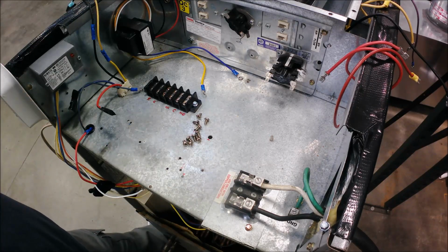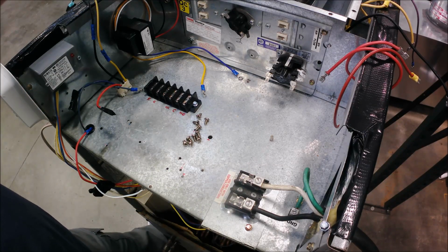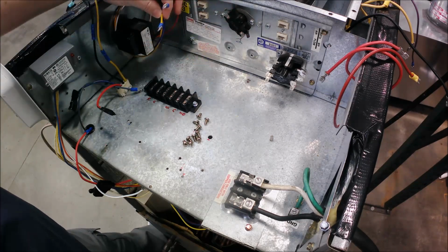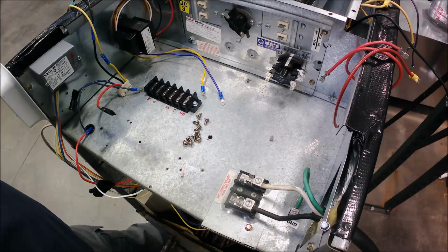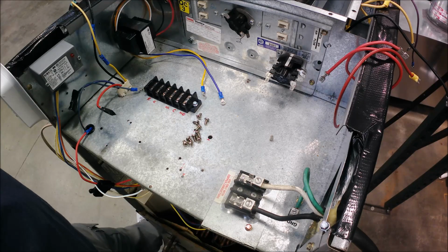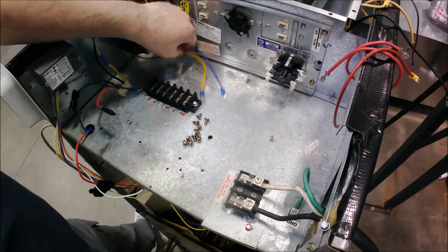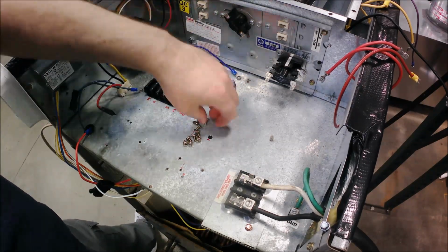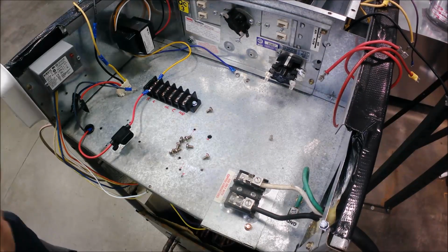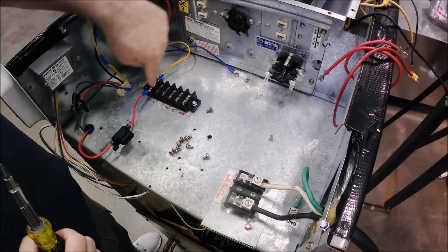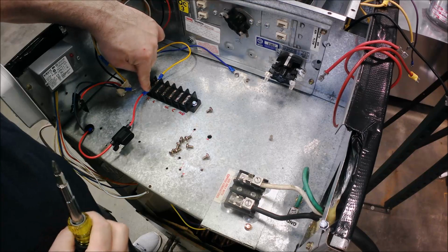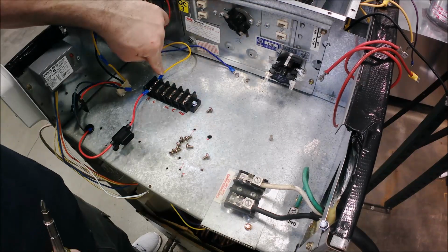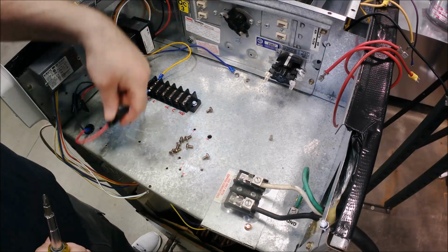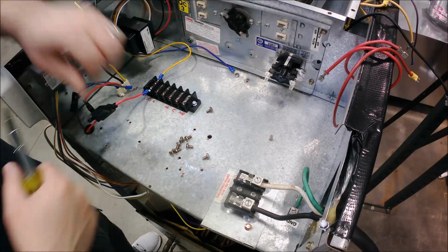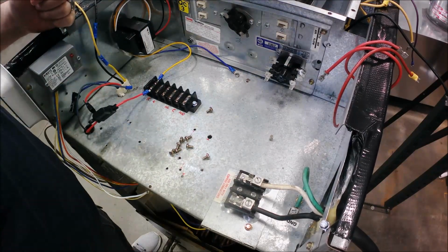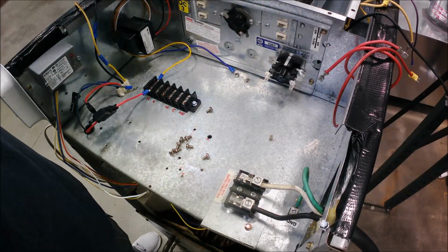So first things first, I'm going to wire my transformer low voltage. Now I've got the high voltage over here, and we'll do the high voltage at one time, but for low voltage we're going to have it all under here. Okay. So we've got our 24 hot connection here, and it's going to go right out of the transformer straight into our fuse holder, down to the thermostat, or the low voltage connections that we're going to do to the thermostat wire.